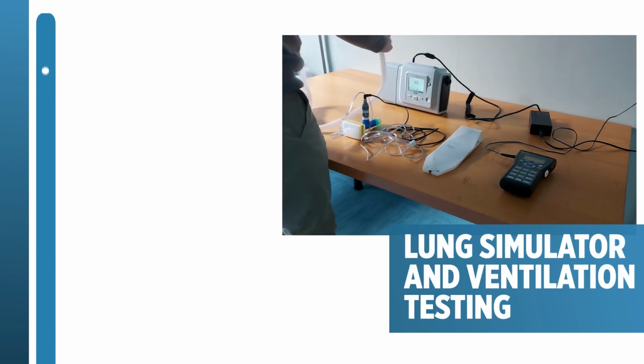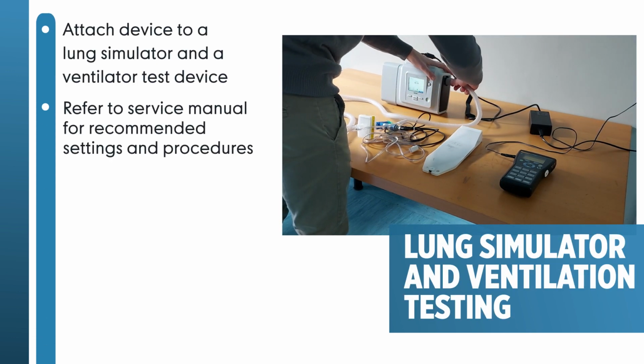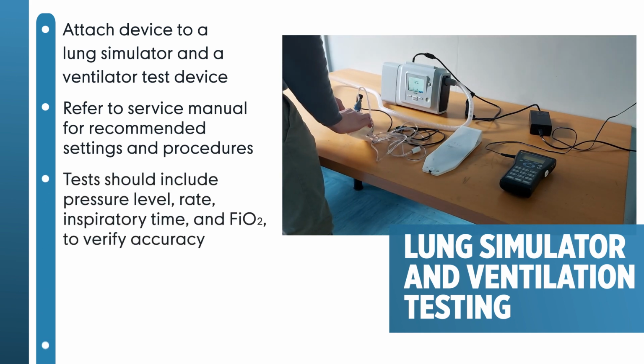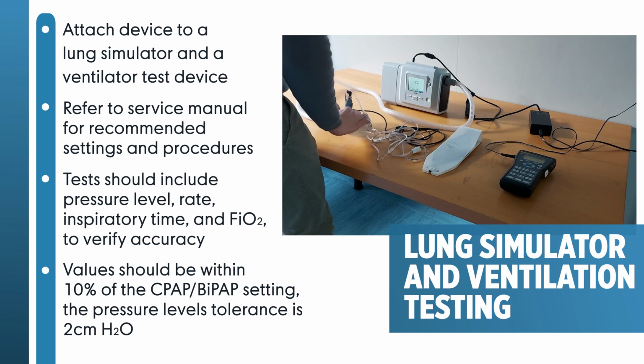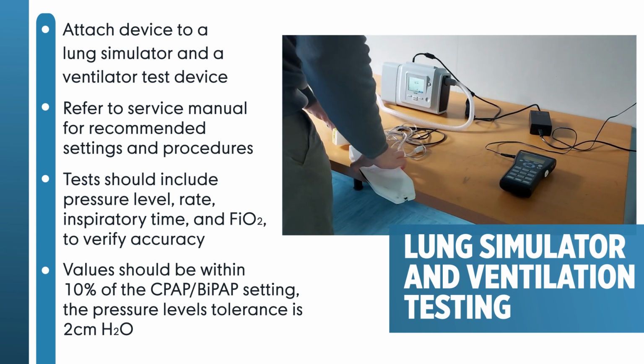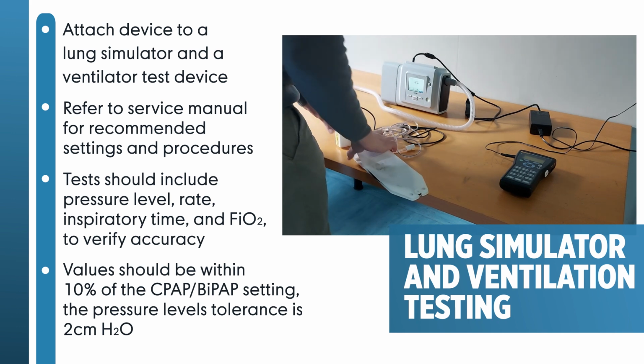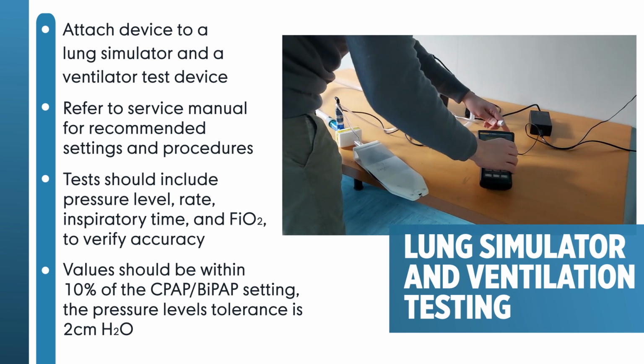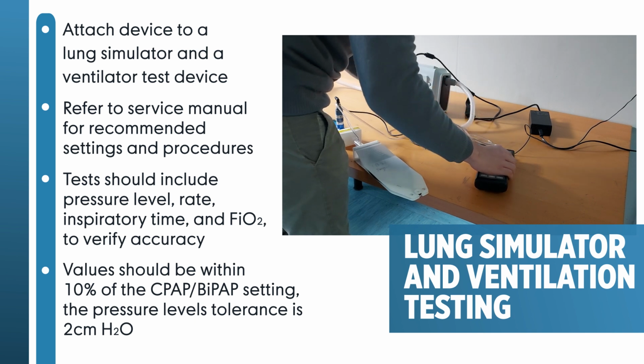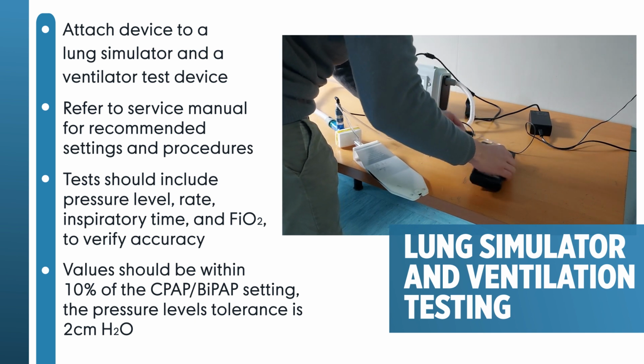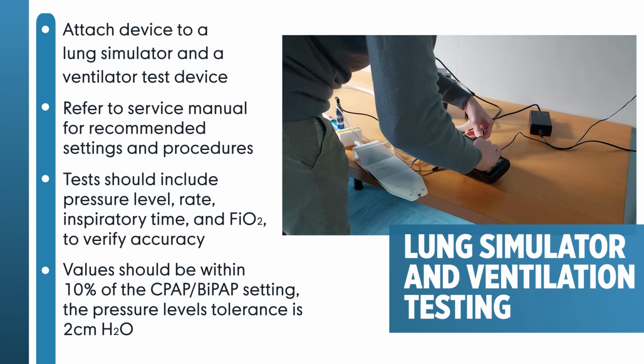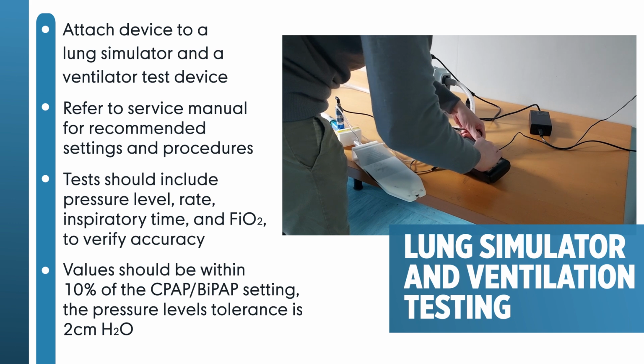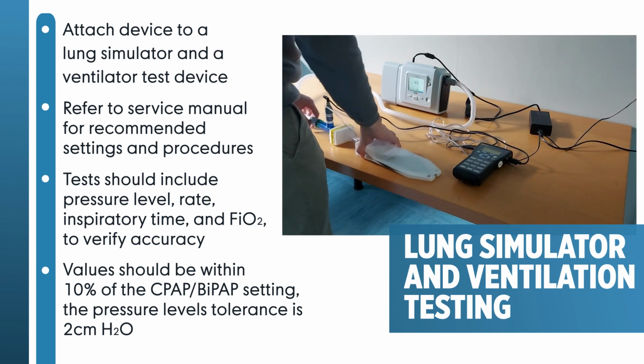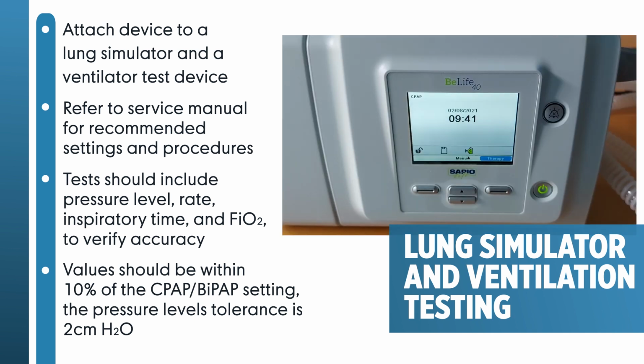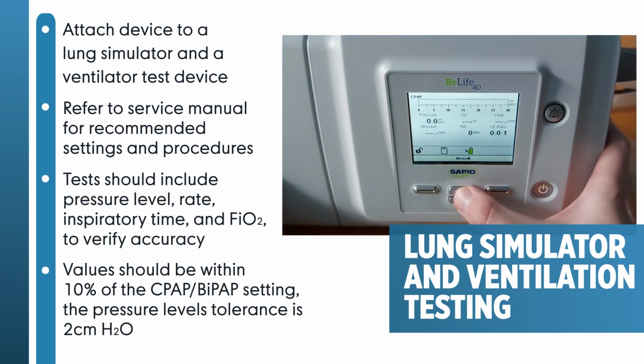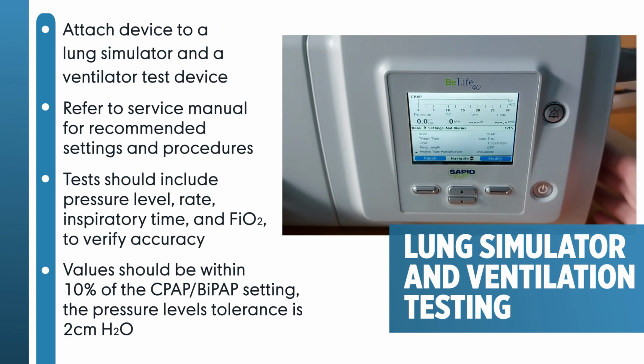Attach the device to a lung simulator and a ventilator tester device if available. Refer to the manufacturer's service manual for recommended settings and procedures. Tests should include pressure level, rate, inspiratory time, and fraction of inspired oxygen to verify proper operation and accuracy. Compare the setting with the values obtained on the ventilator test device. While most values should be within 10% of the CPAP or BiPAP setting, the pressure level's tolerance is 2 centimeters of water pressure. Using the same setup, now we are going to test the equipment in different operational modes.